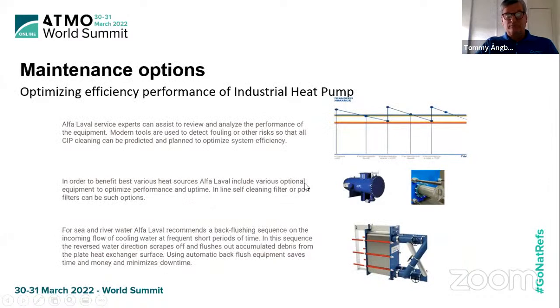And we could also help you discuss and come up with suggestions on how to service the heat exchanger over time, to do connectivity measurements to detect fouling and other risks of the heat exchangers, and maybe also what the best options are when it comes to inline filters or port filters. Especially when you have sea and river water as a heat source, we need to have some kind of backflushing to be sure that we flush out things, animals, small snails or whatever coming into the plant, and that should be done timely, really often, to maintain the efficiency of the heat pump. This we have and can discuss with you.